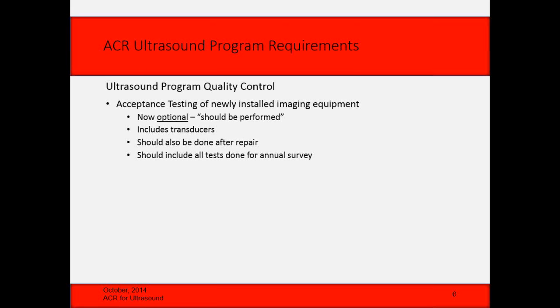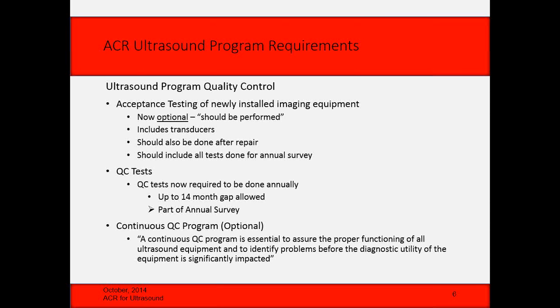QC tests are now required to be done annually. You can have up to a 14-month gap, and it needs to be submitted as part of that annual survey. And then a continuous QC program is now optional. But what the ACR says about it, I would definitely back that up, which is a continuous QC program is essential to assure that everything's working correctly, and also to identify problems before the system isn't able to be used for diagnosis. In other words, let's make the uptime as good as possible, and let's make sure it's working properly. And frankly, it's a little hard to disagree with that, but it is optional to do that now.